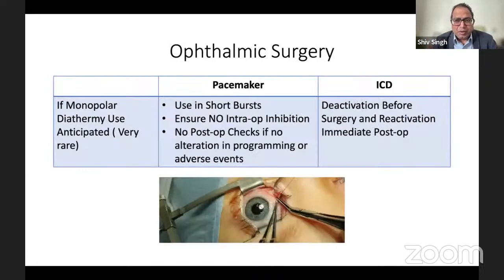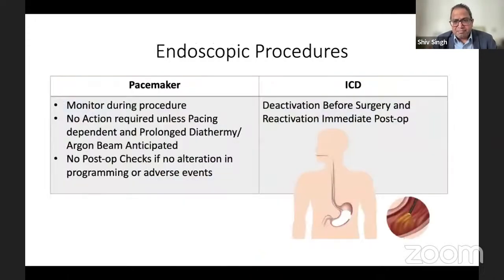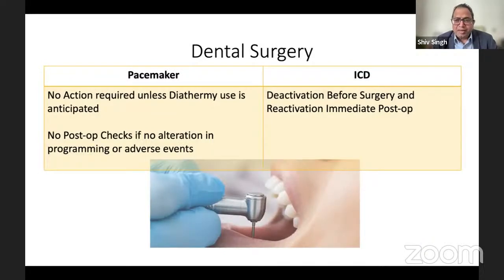Ophthalmic surgery, you're working on the eye, in a very small area. They hardly use monopolar. I don't think they ever use monopolar for that matter. It is close to the eyes, especially if the pacemaker unit is on the left side and you're operating on the left eye, then ask the surgeons to use diathermy in short bursts. It's bipolar, obviously. And if there have been no changes in the rhythm, there's no need for a post-operative check. Endoscopic procedures, again, you monitor them during the procedure. There's no requirement for changing any settings, and no need for post-op checks at all. Dental surgery, they hardly use diathermy. Again, they use chemical cautery. That's my experience. And so no need for any checks at all.